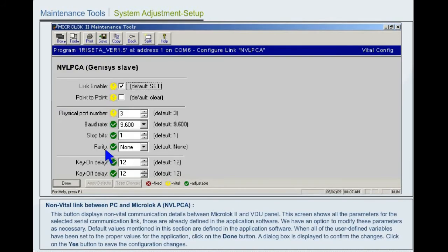Non-vital link between PC and Microlok A. This button displays non-vital communication details between Microlok II and the Visual Display Unit panel. This screen shows all the parameters for the selected serial communication link. Those are already defined in the application software. We have an option to modify these parameters as necessary. Default values mentioned in this section are defined in the application software.